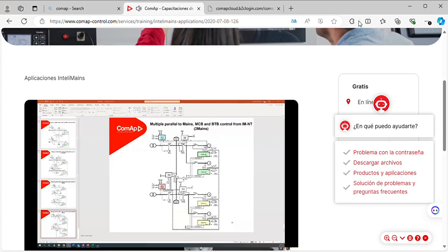And if you want to see the synchroscope or anything, you can just go down. You can see the parameters. So it's already synchronized. So they're feeding up the load here. So basically I have the top 3 gensets running. The fourth one is out of the bus.